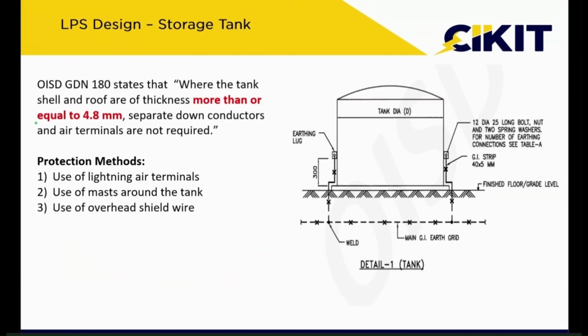So this is the reference provided by the standard OISD GDN 180. So we will be using these three methodologies, specifically those two methodologies, for these storage tanks. OISD GDN 180 states that if the tank wall thickness is more than 4.8 mm, then there is no need for providing an additional air termination system and down conductors. We can directly connect the body of the tank to the ground. That itself is more than sufficient, because if lightning strikes the tank itself, the temperature increase won't be that much and it won't result in an explosion at all. So the body itself can act as a natural component of the lightning protection system.